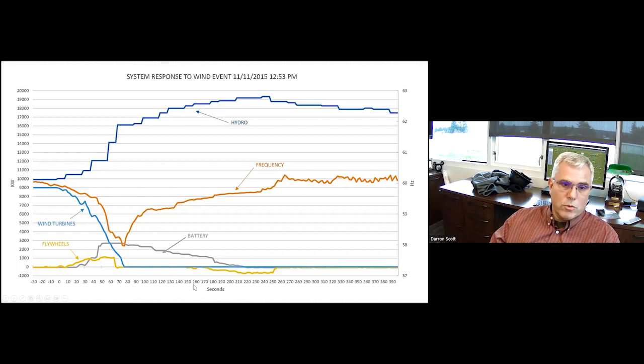This also showed this point right here, which is just about 58 hertz. If we'd gotten just a little bit lower, we would have started cutting off customers. So we knew we had really designed this as far as we could go—we really couldn't add more wind to the system under this configuration. In some ways, it made us feel really good that we'd dialed in as far as we could and gotten as much out of the system as we had, because things don't get much worse than basically 50% of your system load just going away in a matter of a few seconds.